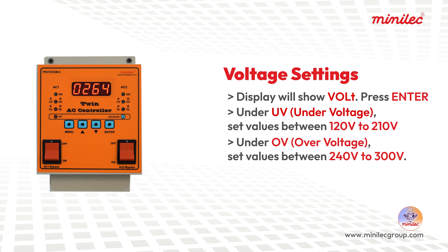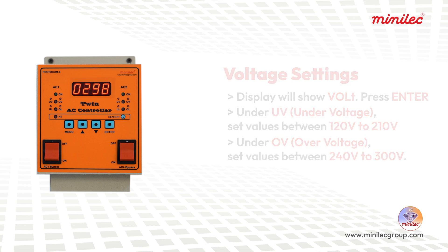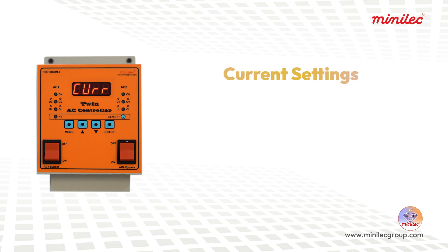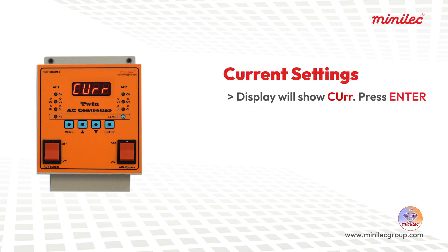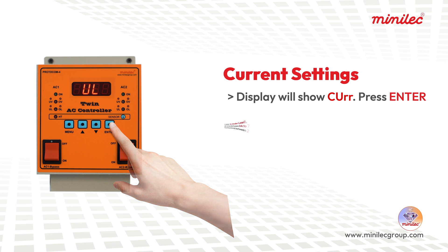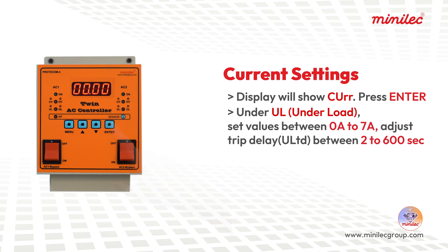Current settings: When the display shows CUR, press ENTER. Under UL (under-load), set values between 0A to 7A and adjust the trip delay between 2 to 600 seconds.